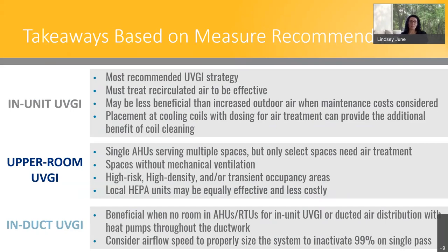Upper room UVGI is a good application for buildings where single air handling units serve multiple spaces, but only certain spaces need enhanced airborne exposure mitigation. Upper room can be more cost effective than installing a new mechanical ventilation system for spaces that don't currently have mechanical or passive ventilation capabilities. Upper room is also good for high risk, high density, and or transient occupancy areas, such as nurses' offices, lobbies, lounges, locker rooms, open or shared office spaces, conference rooms, kitchens, cafeterias, restrooms, or corridors. And then local HEPA filtration units may be equally effective and less costly to install and maintain than upper room UVGI.